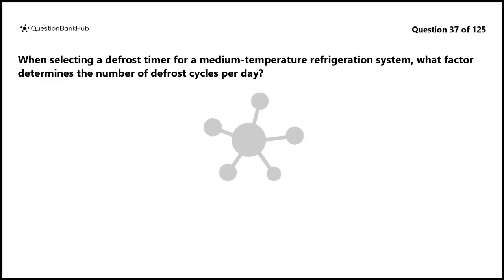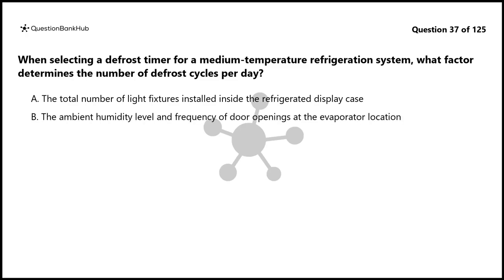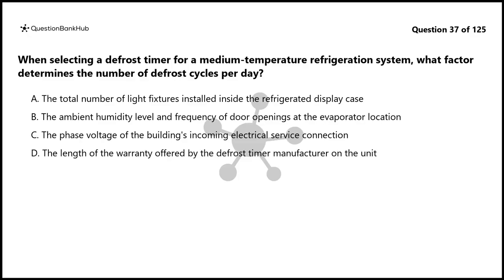Question 37. When selecting a defrost timer for a medium temperature refrigeration system, what factor determines the number of defrost cycles per day? A. The total number of light fixtures installed inside the refrigerated display case. B. The ambient humidity level and frequency of door openings at the evaporator location. C. The phase voltage of the building's incoming electrical service connection. D. The length of the warranty offered by the defrost timer manufacturer on the unit.